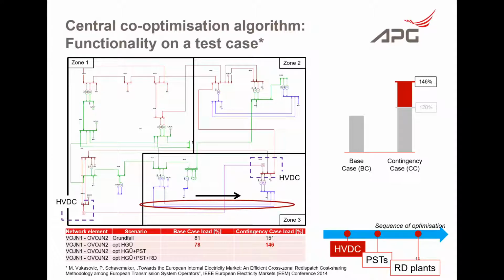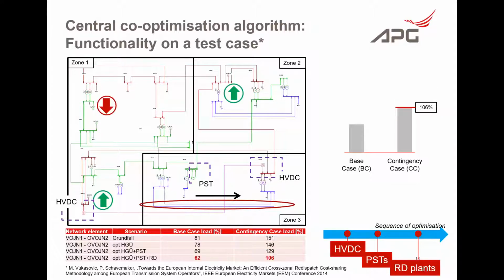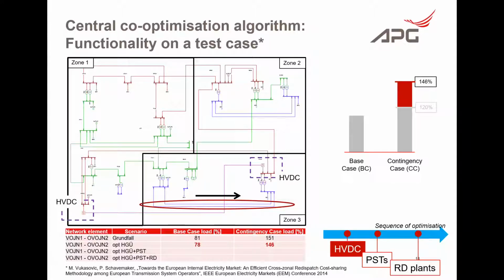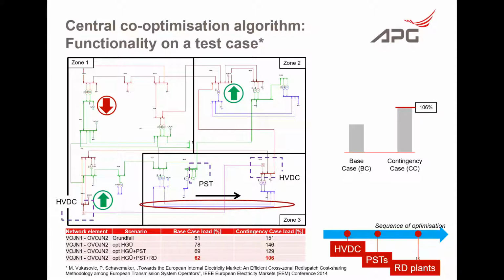You go further with changing the PST taps, and the lines are even more relieved. At the end, due to activation of redispatch, you go down to 106% of line loading in the N-1 case. You can really see that, due to coordinated activation, we try to minimize cost and put everything in place in the most economically efficient way. This is what we are doing currently.